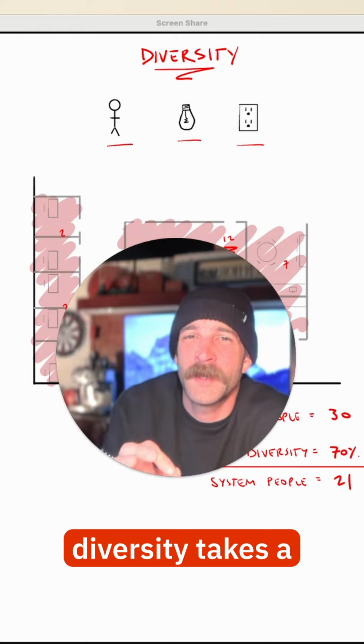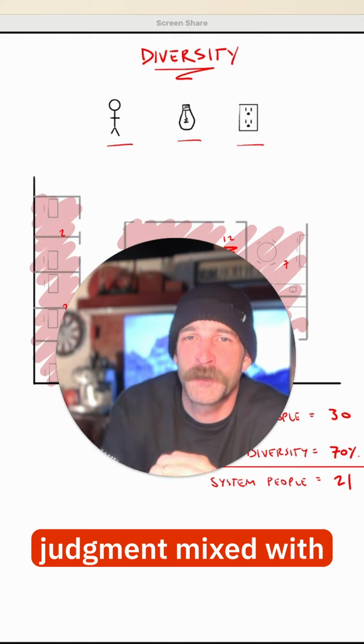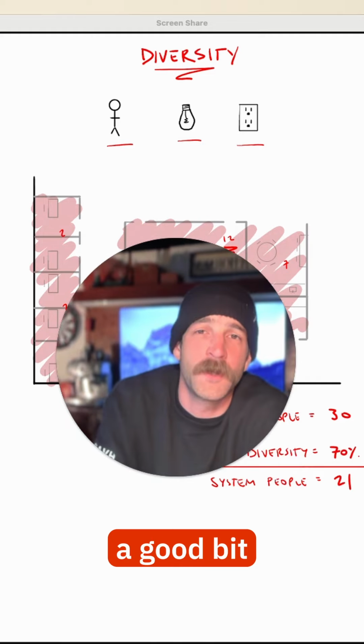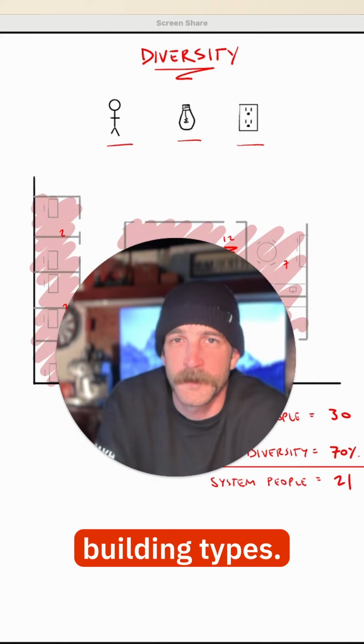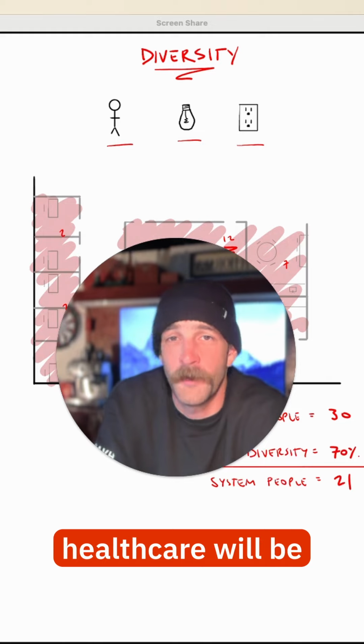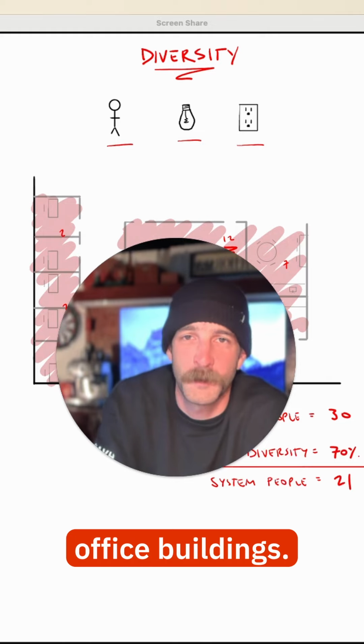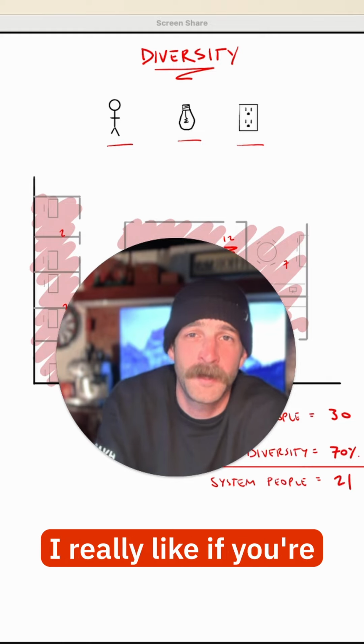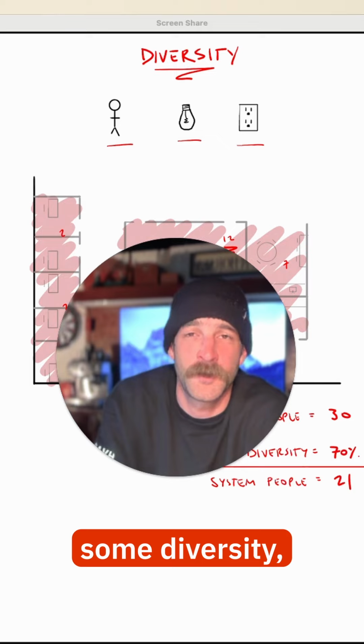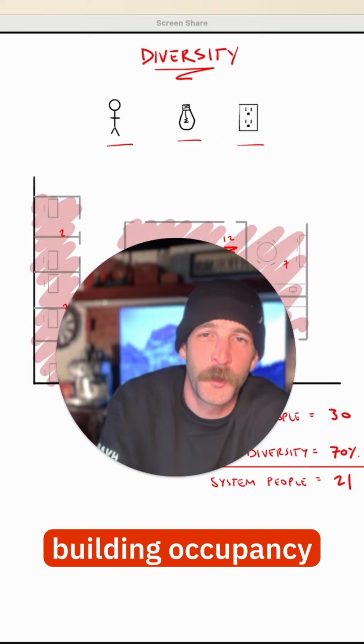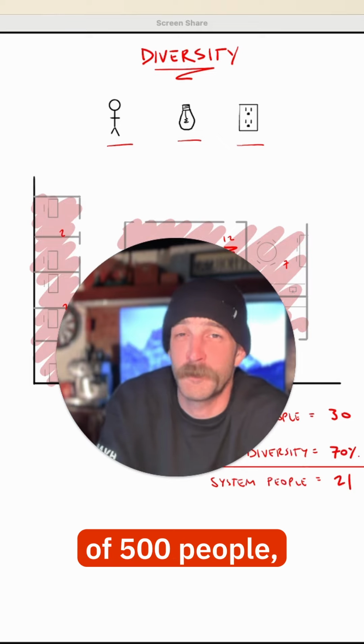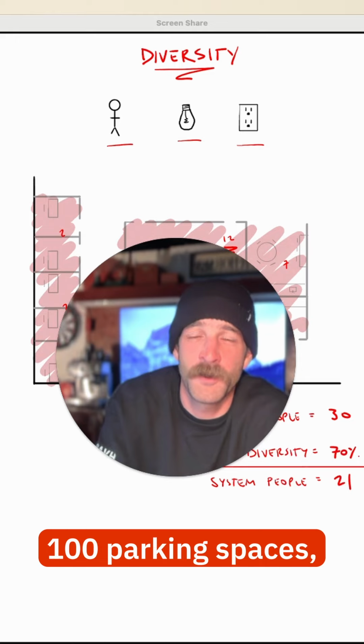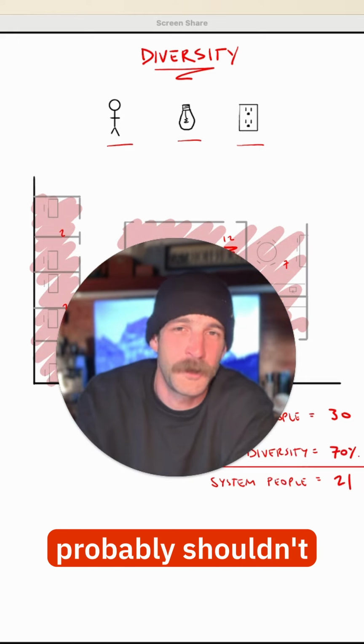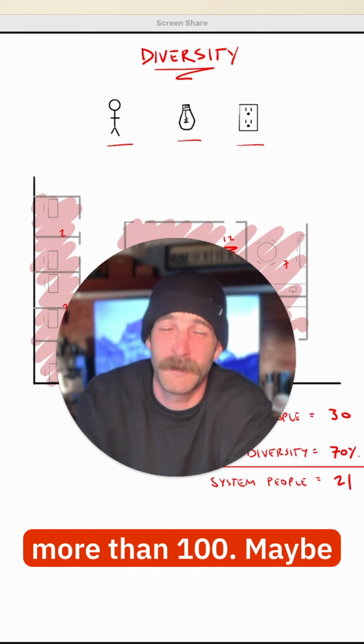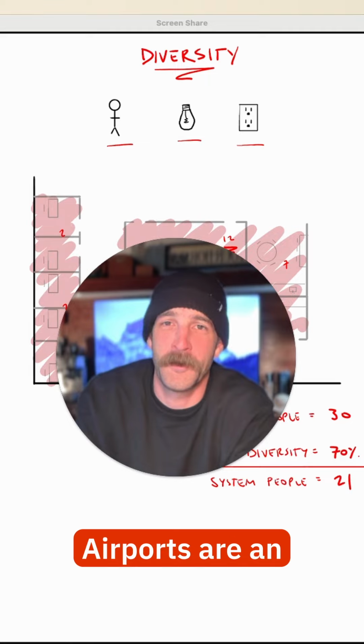Choosing the right diversity takes a little engineering judgment mixed with some common sense, and it varies a good bit based on building types. Education will be different from healthcare, will be different from office buildings. But one pro tip I really like, if you're trying to justify some diversity, look at the parking lot. If you have a total building occupancy of 500 people, but there are only 100 parking spaces, then you probably shouldn't expect a whole lot more than 100, maybe 200 people. Airports are an obvious exception.